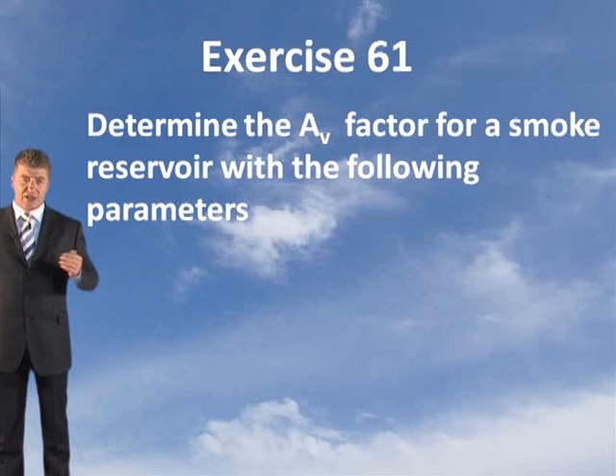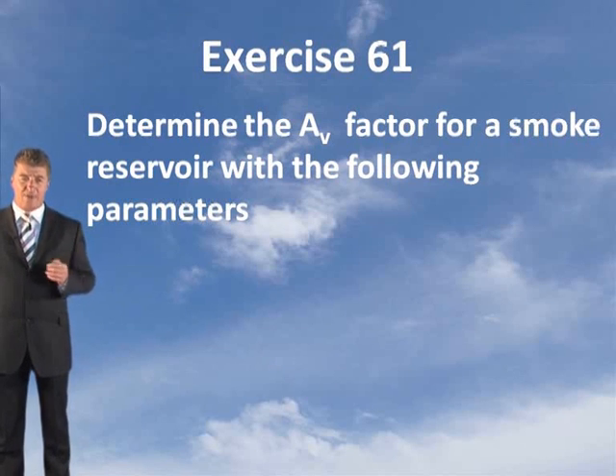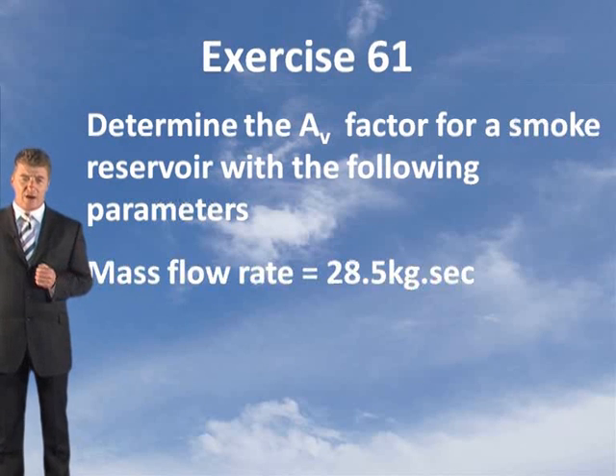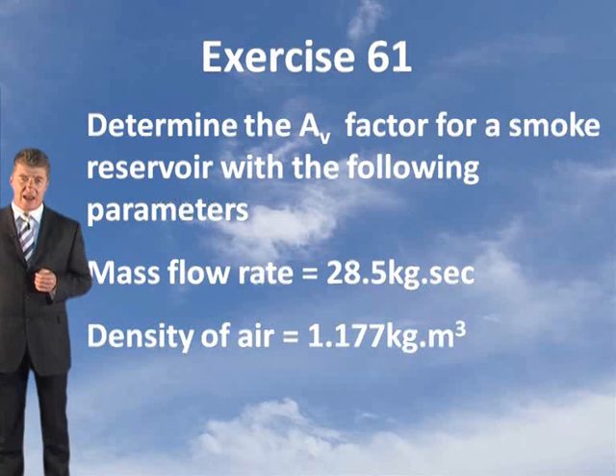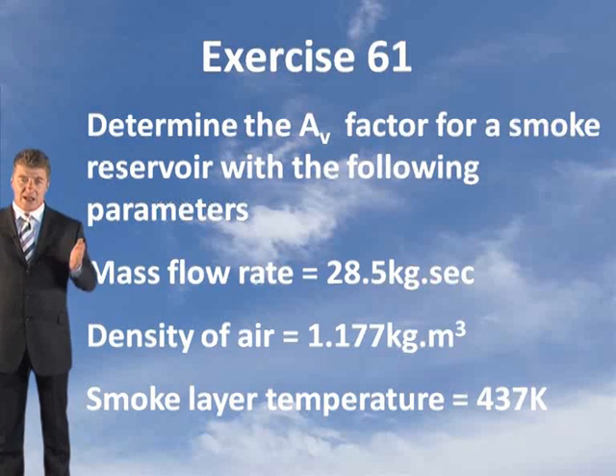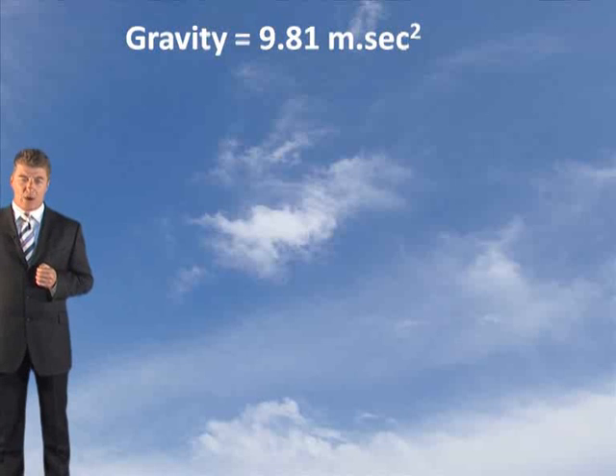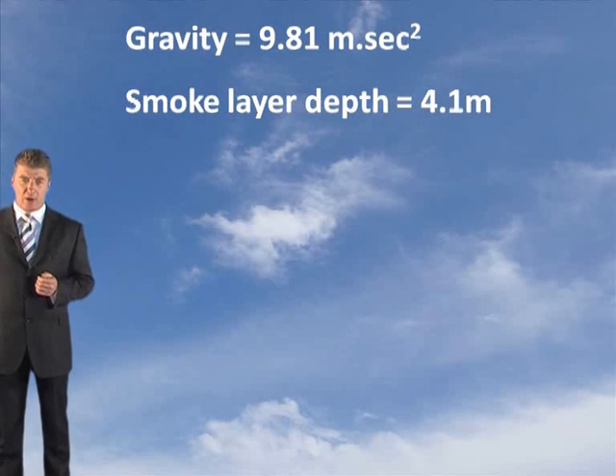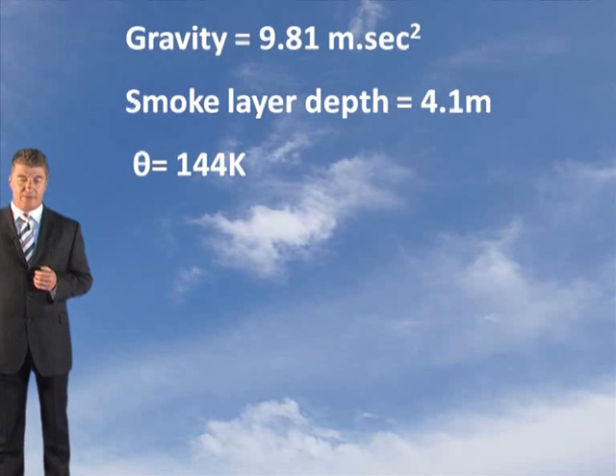Exercise. Determine the AV factor for a smoke reservoir with the following parameters. Your mass flow rate of smoke is 28.5 kilograms per second. Your density of air is 1.177 kilograms per meter cubed. Your temperature of your smoke layer was worked out at 437 degrees Kelvin. Acceleration due to gravity is 9.81 meters per second squared. Your smoke layer depth is 4.1 meters and your theta value is 144 degrees Kelvin.